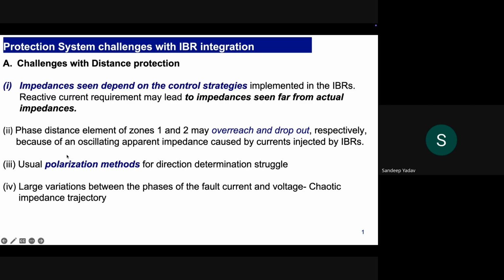The usual polarization method. We know that the relays are polarized in order to determine the direction of the fault, whether the fault is in the forward direction or the reverse direction. There are polarization methods in place which work on the basis of phase relationship between current and voltage. In case of conventional sources, the current and voltage usually have a predictable phase relationship depending upon the grounding of the system and the unbalances in the system. They are largely predictable. So all these polarization methods struggle when it comes to determining the direction in case of fault current fed by the IBRs.